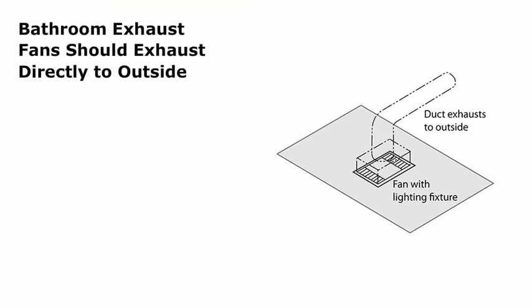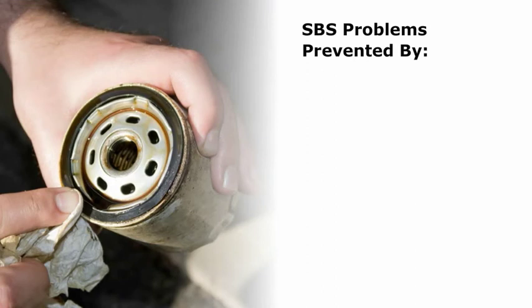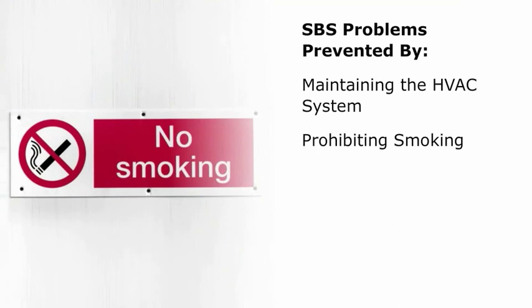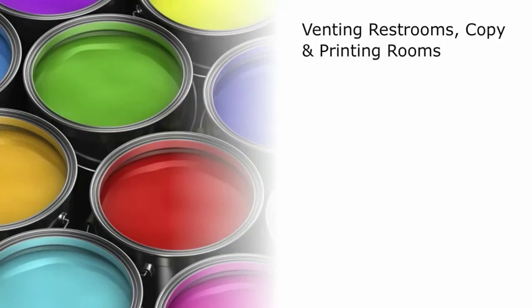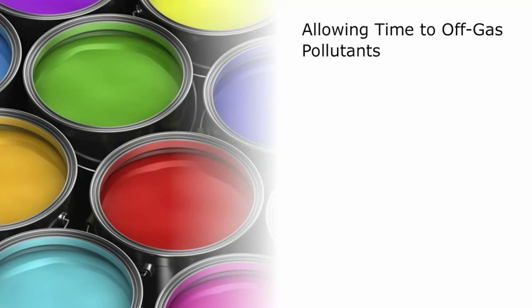Bathroom exhaust fans should exhaust directly to the outside. Many of the problems people have with adverse reactions to building contaminants develop after new construction or renovation. Renovations in occupied buildings are especially likely to introduce pollutants into the building's interiors. SBS problems can be prevented by maintaining the HVAC system including periodic filter replacement, replacing water-stained ceiling tile and carpet, prohibiting smoking, venting restrooms, copy rooms, and printing facilities to the outside, storing and using paints, adhesives, solvents, and pesticides in well-ventilated areas or unoccupied spaces, and allowing time for building materials in new or remodeled areas to off-gas pollutants before occupancy.